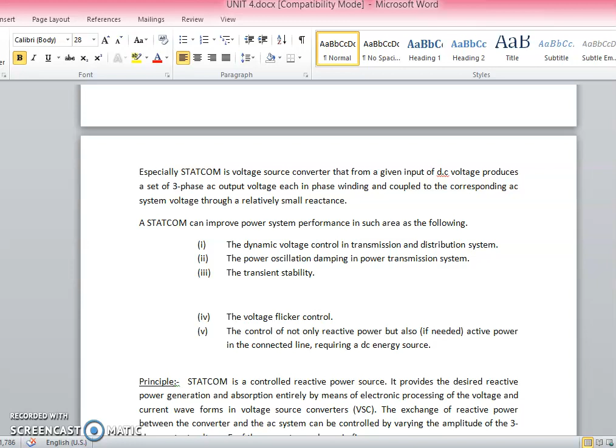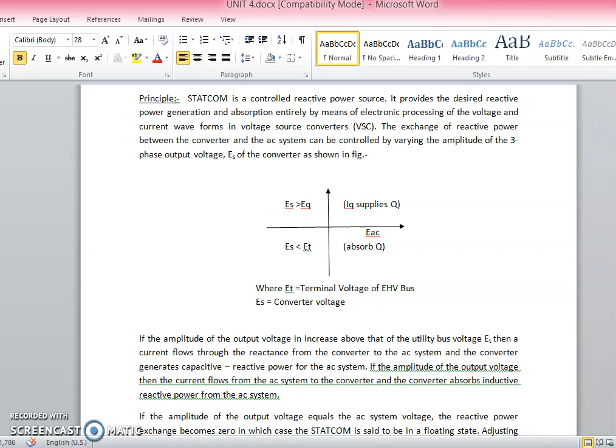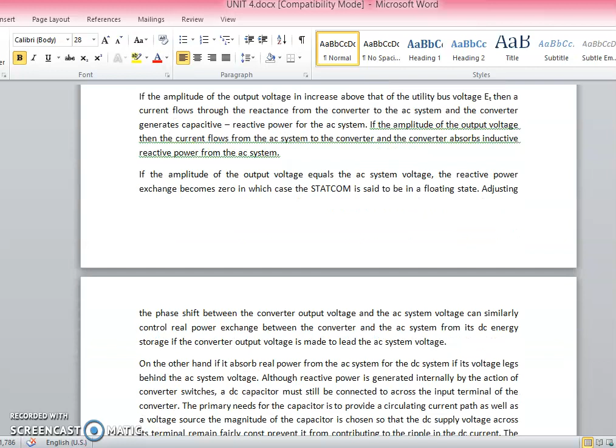This is the diagram in four quadrants. If the amplitude of the output voltage is increased above that of the utility bus voltage, then current flows through the reactance from the converter to the AC system, and the converter generates capacitive reactive power for the AC system. If the amplitude of the output voltage is decreased below the bus voltage, then the current flows from the AC system to the converter, and the converter absorbs inductive reactive power from the AC system. If the amplitude of the output voltage equals the AC system voltage, the reactive power exchange becomes zero, in which case the STATCOM is said to be in a floating state.